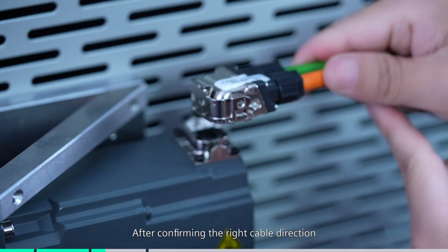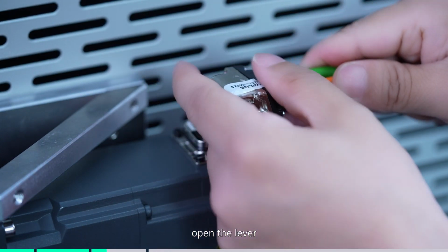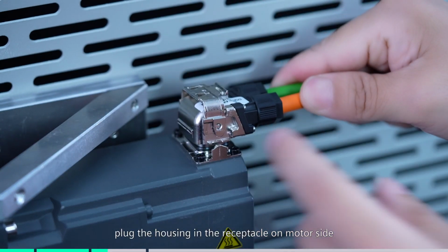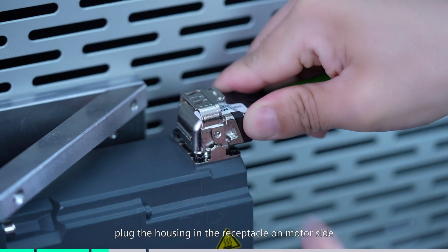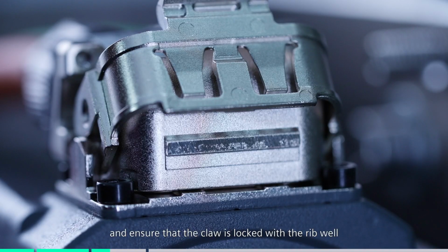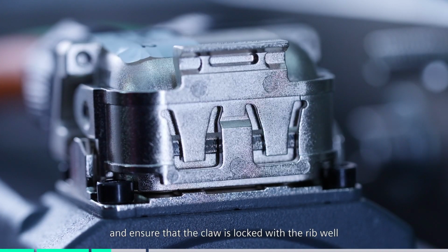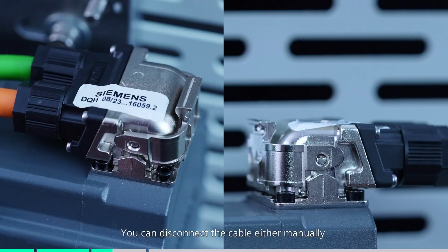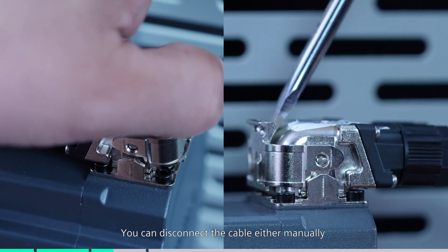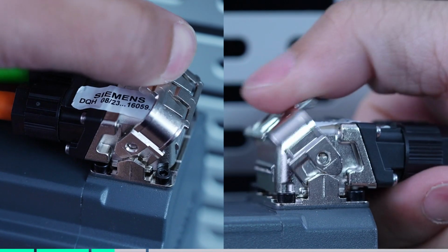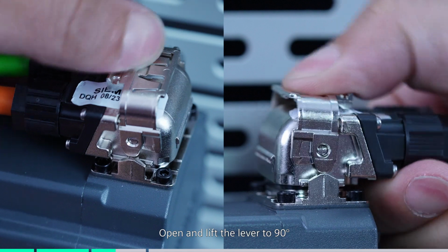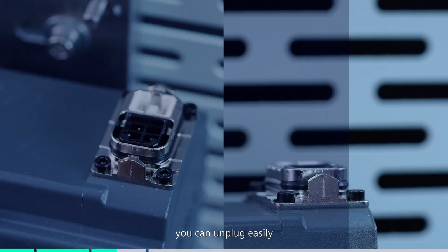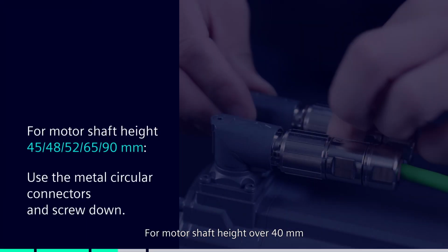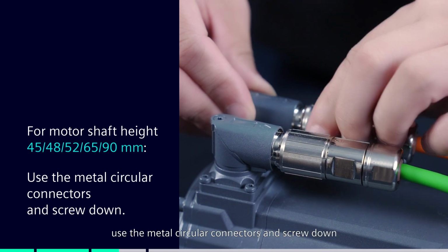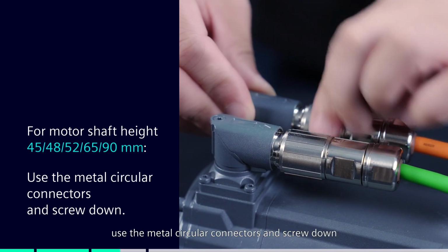After confirming the right cable direction, open the lever, plug the housing in the receptacle on motor side, push and lock the lever, and ensure that the claw is locked with the rib well. You can disconnect the cable either manually or with a screwdriver. Open and lift the lever to 90 degrees. You can unplug easily. For motor shaft height over 40 mm, use the metal circular connectors and screw down.